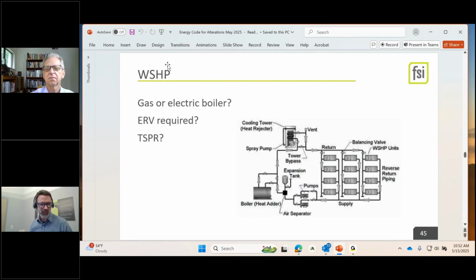We are seeing an interesting hybrid now with the refrigerant changeout, where you run a water source loop to floor-by-floor water cooled condensers and then do VRF out on the floor level where you don't have to build fireproof chases. So water source heat pump has made an interesting reintroduction. I've got some young engineers who've never done one, but we're doing it now because we can't run refrigerant more than 2 floors without jumping through a bunch of hoops.